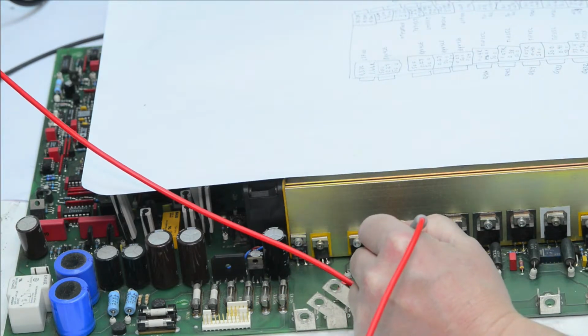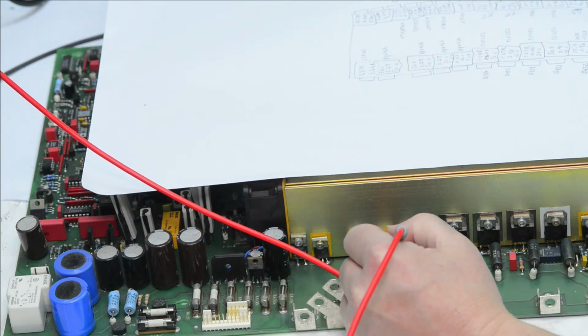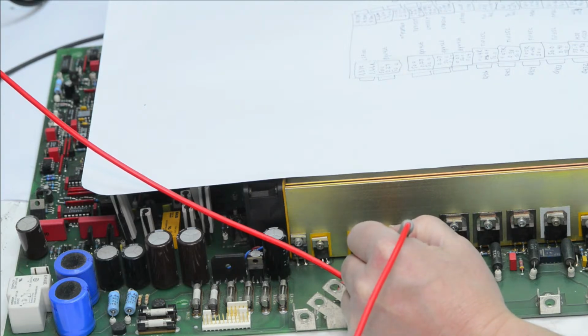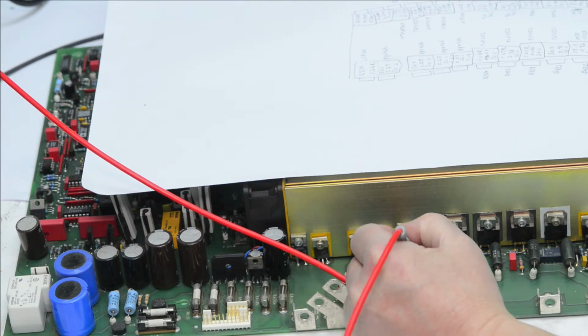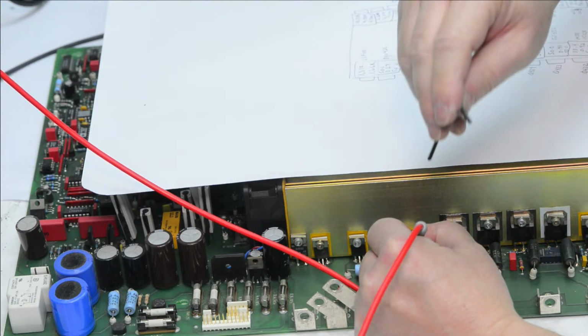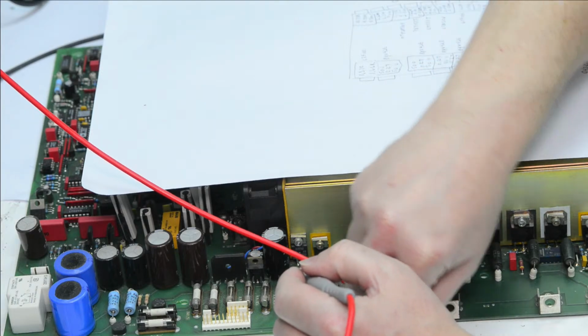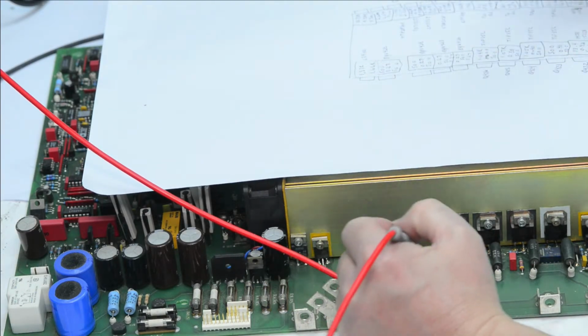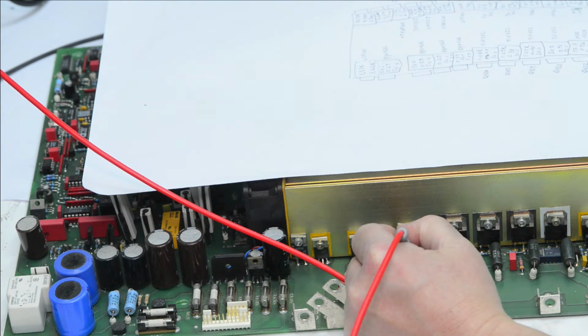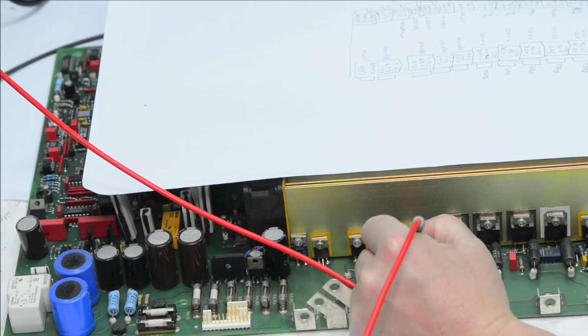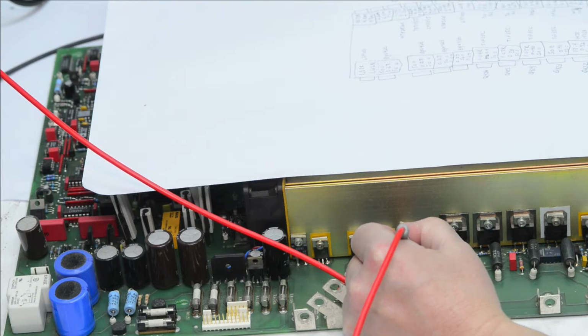And when the IEC source was programmed to limit the current, even 10 amp input current was tripping out on power on. But that's likely because of the inrush and the charge current of those big capacitors. That's possible. So I had to set up the Chroma source to a 16 amp maximum current limit to successfully boot up this Wavetek 9100.